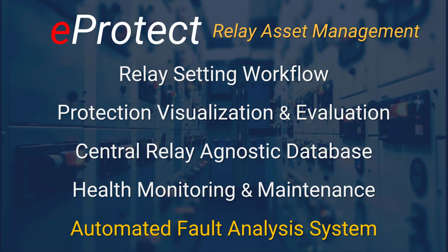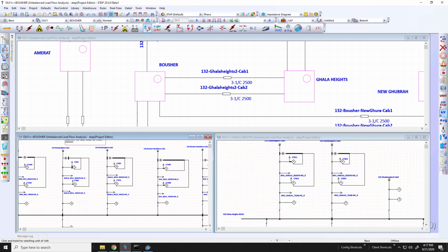Now let's look at a quick demo of the automated fault analysis system, AFAST. The AFAST product allows for the analysis of COMTRADE files for multiple different relays to help properly locate where a fault might be. For example, on the top portion of this one-line diagram, we have 2 substations, one here, and transmission lines in between. If I zoom in to one of these substations, here we can see a number of relays feeding that transmission line. There are also a lot more relays in that same transmission substation.